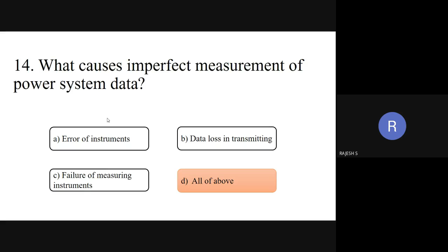Okay, error and failure are different. Failure means it is totally shut down, the equipment is not working. An error means a slight deviation from the correct reading. In first year you did the experiment of calibration of an energy meter. From that experiment we observe how accurately the energy meter reads according to its standard value. With the help of that standard value we check whether it is an error or not. So that has to be considered.